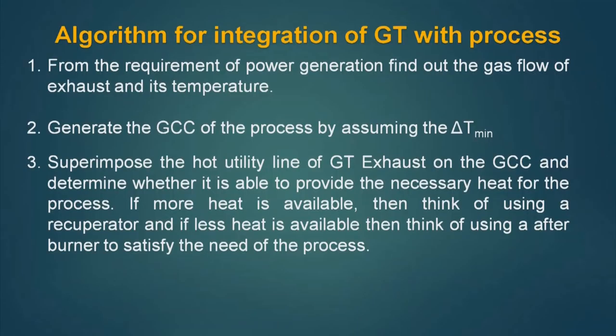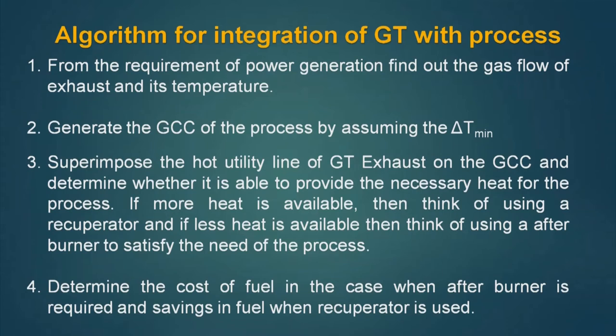Number three: superimpose the hot utility line of GT exhaust on the GCC and determine whether it is able to provide the necessary heat for the process. If less heat is available, think of using an afterburner to satisfy the need of the process. Fourth point: determine the cost of fuel in the case when an afterburner is required and savings in fuel when a recuperator is used. All our decisions will be based on economic analysis using the TAC — total annual cost — of the integrated system, and we will select the system which gives us the best profit.